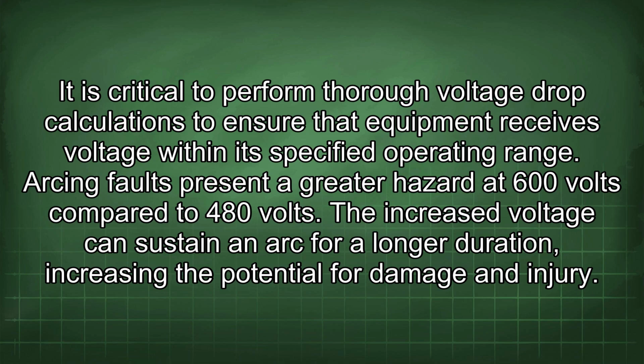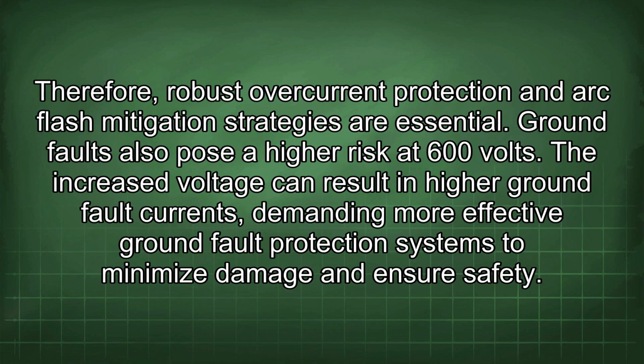Arcing faults present a greater hazard at 600 volts compared to 480 volts. The increased voltage can sustain an arc for a longer duration, increasing the potential for damage and injury. Therefore, robust overcurrent protection and arc flash mitigation strategies are essential. Ground faults also pose a higher risk at 600 volts.